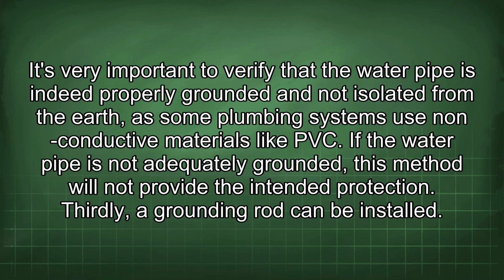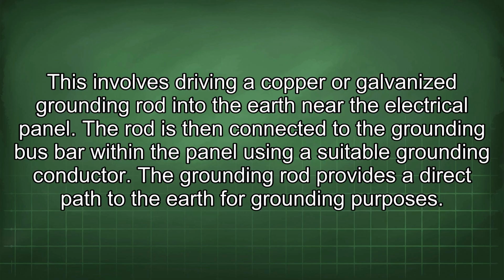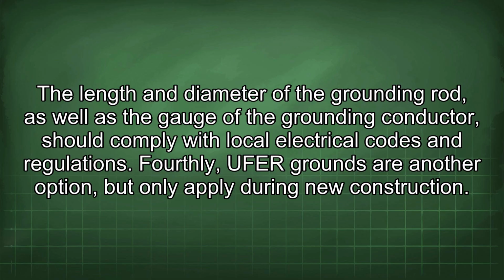Thirdly, a grounding rod can be installed. This involves driving a copper or galvanized grounding rod into the earth near the electrical panel. The rod is then connected to the grounding bus bar within the panel using a suitable grounding conductor. The grounding rod provides a direct path to the earth for grounding purposes. The length and diameter of the grounding rod, as well as the gauge of the grounding conductor, should comply with local electrical codes and regulations.